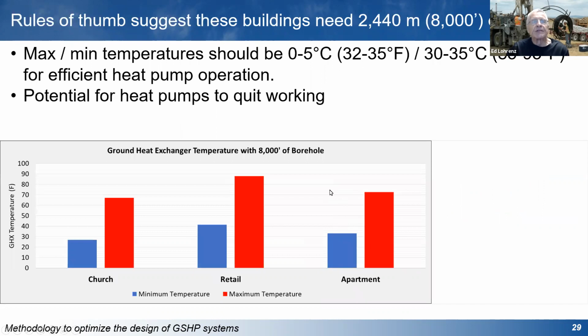So if we use rules of thumb on, let's say, one of these buildings at 40 tons capacity, it would suggest that you need about 8,000 feet of drilling. And you're trying to maintain temperatures somewhere around 32 to 35 degrees Fahrenheit on the heating side, and about 85 to 95 when you're cooling the building. Otherwise, the heat pumps start operating less and less efficiently.